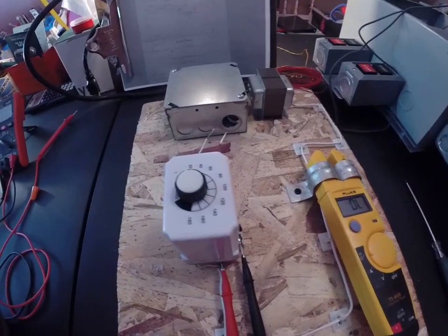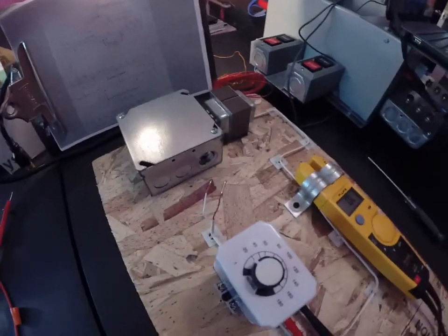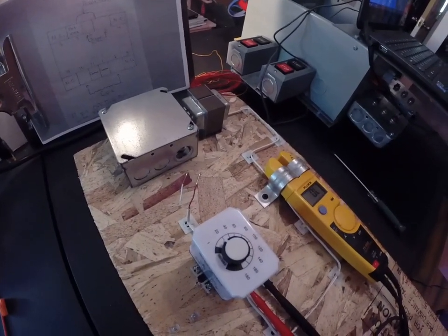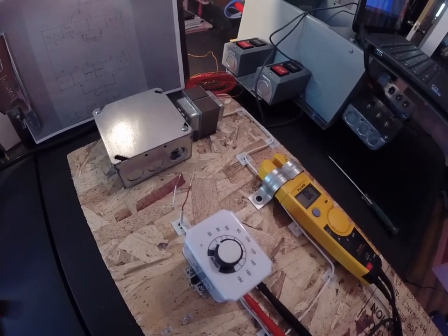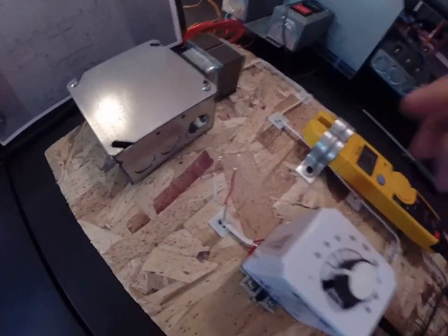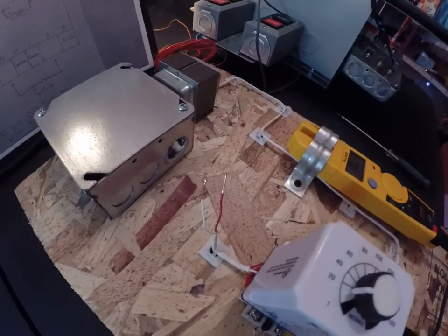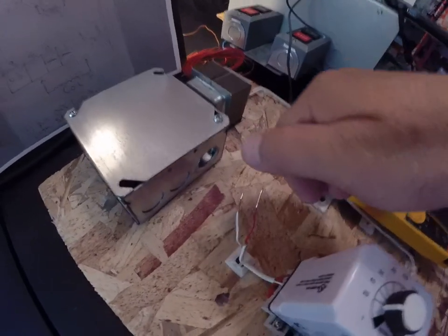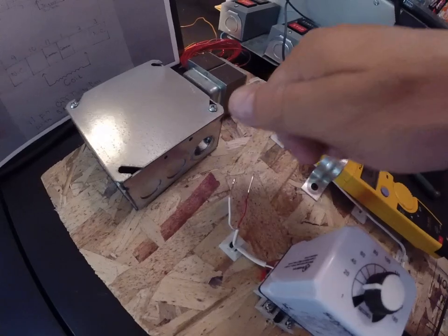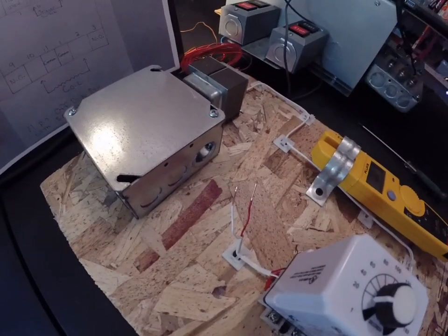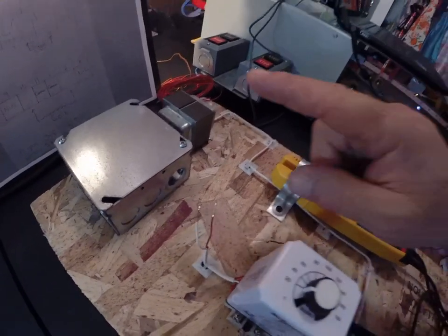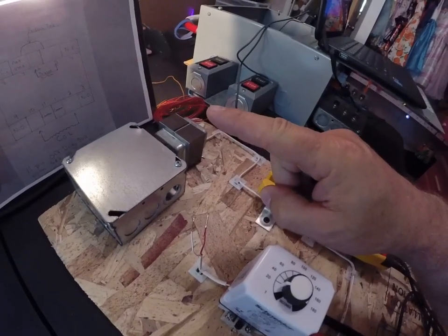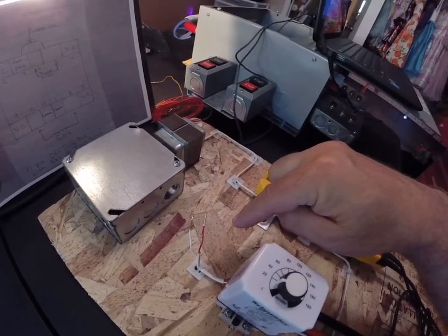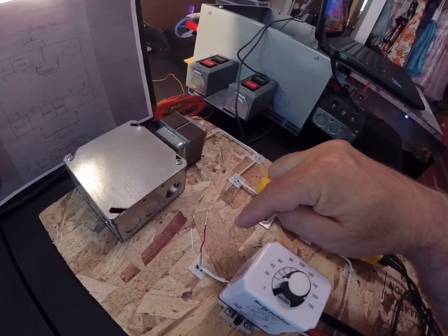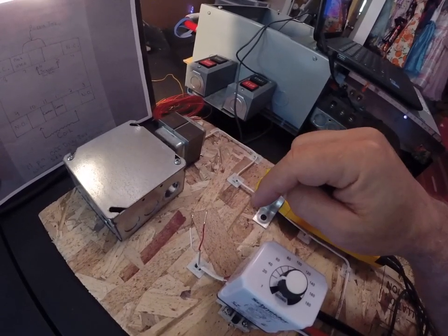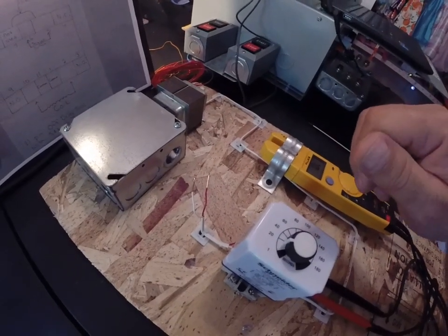There it goes. So it timed out. So it's the removal of the short circuit that starts the timed off response. So let's do it again. Right now, the coil's energized. It does nothing until you create this short circuit. And when I do this, I want you to think of the basketball hoop. The limit switch, once the ball goes by that limit switch, it closes that normally open contact just for a second. But then the spring returns it, allowing the off delay to do its thing.